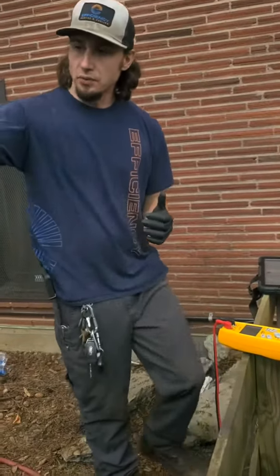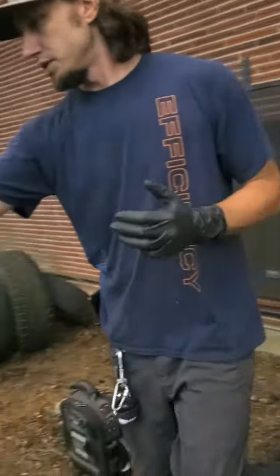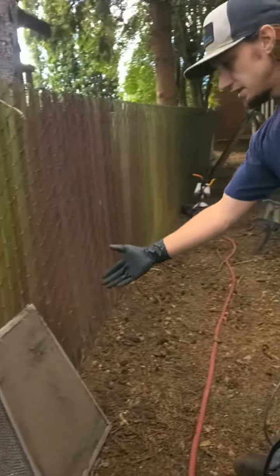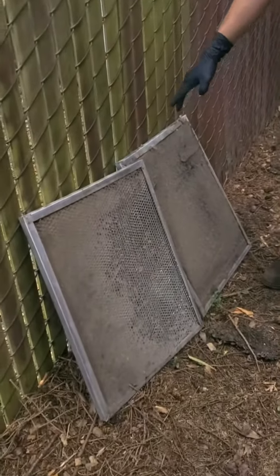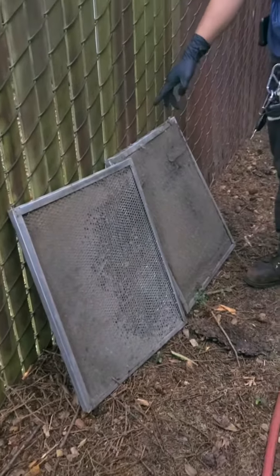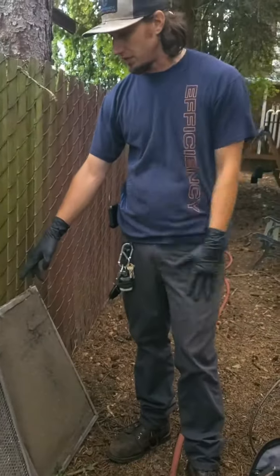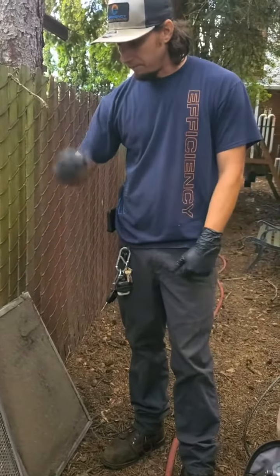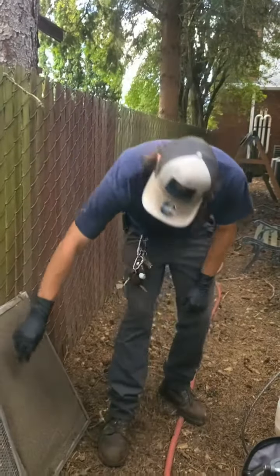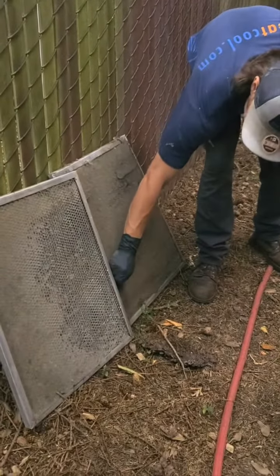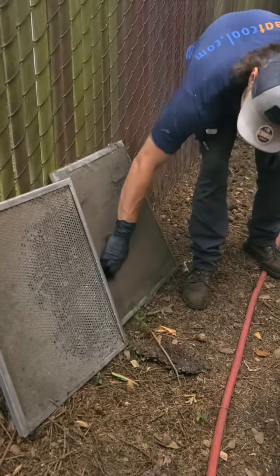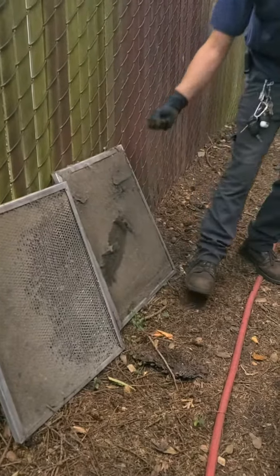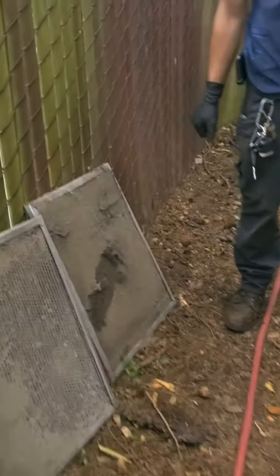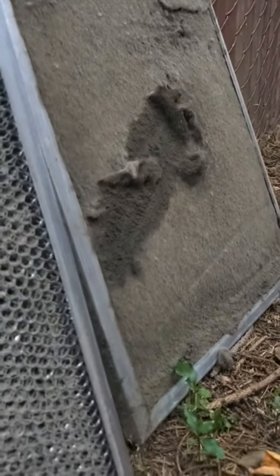per ton. So I went digging through here, and what we found was a second set of filters tucked behind the equipment, because this system has a fresh air intake right over here next to the flue exhausts. And so they were trying to filter this. I don't think anyone's been taking care of this thing for a while. As you can see here, the dirt on these filters is pretty intense. I don't think they've been touched for years.